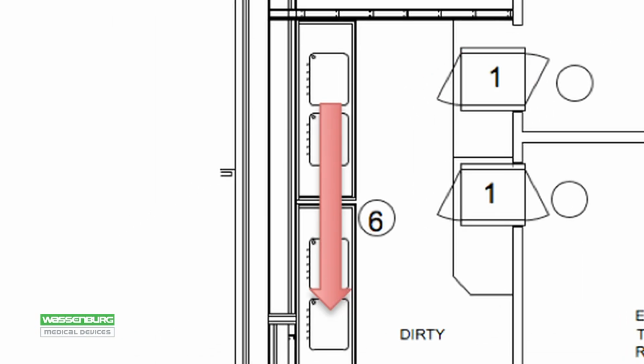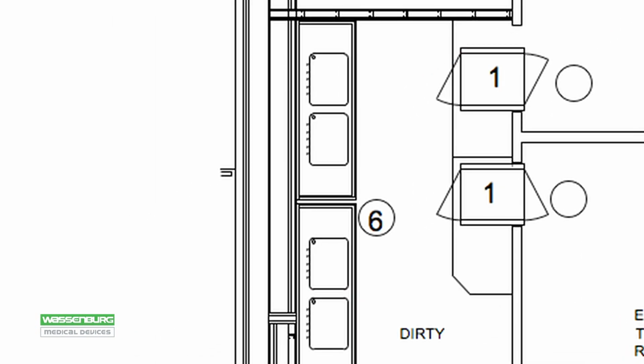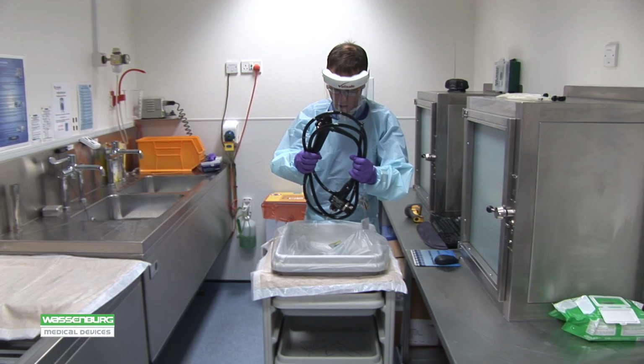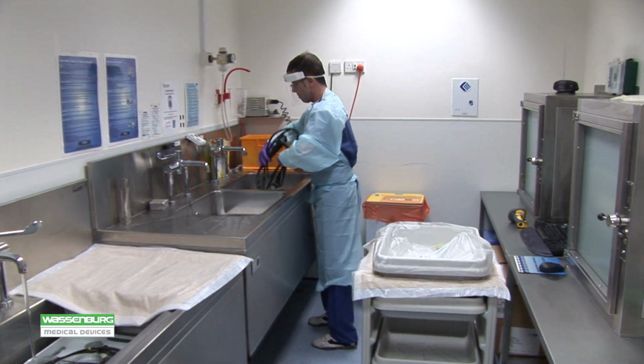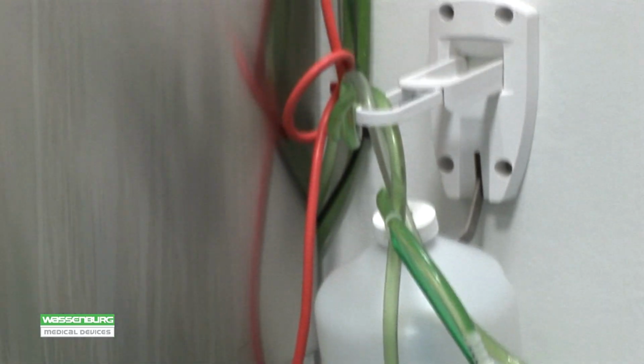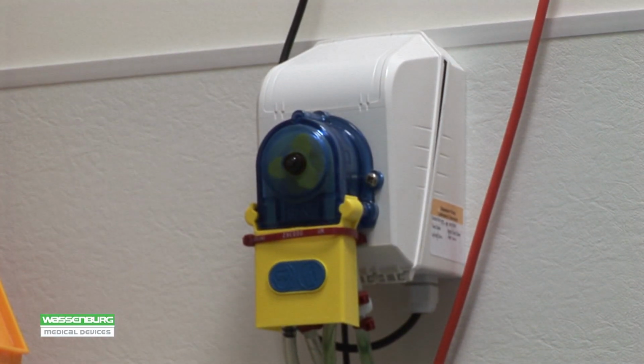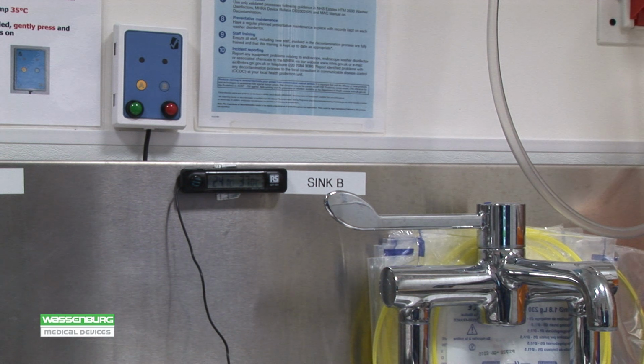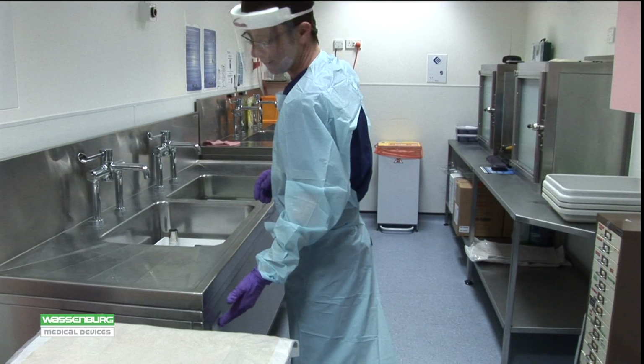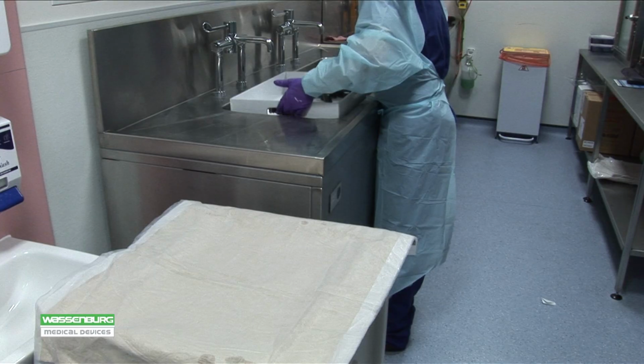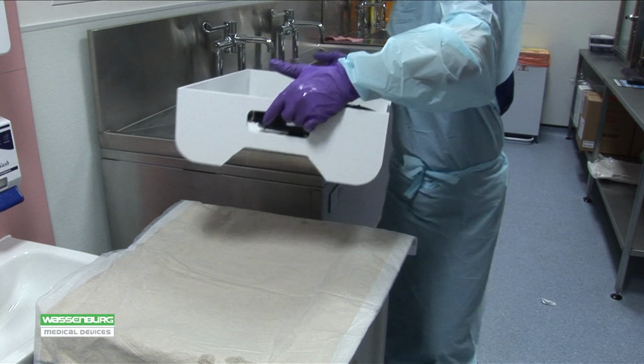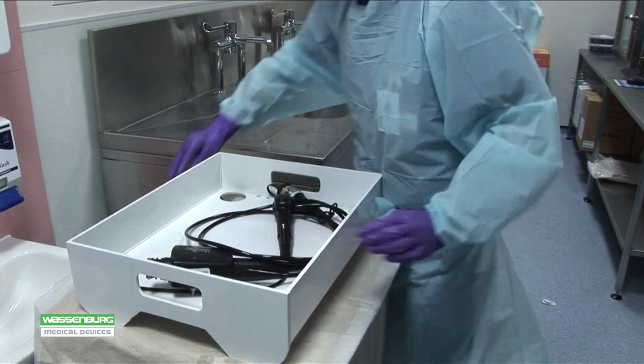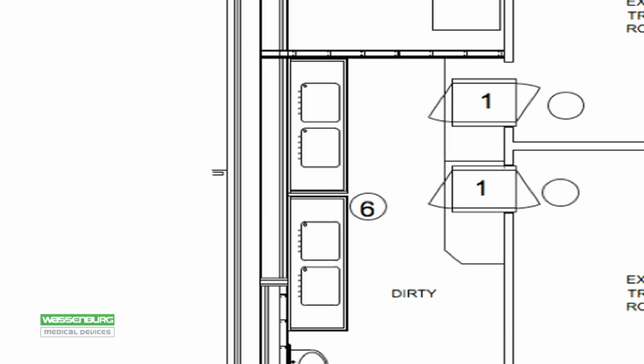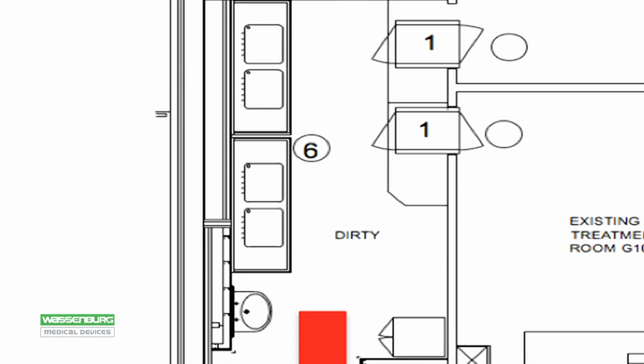Scopes are transferred to the adjustable height double sinks for manual cleaning, followed by rinsing in a separate bowl. Detergent is automatically dispensed in the correct volume to the wash sink by calibrated pump. Sink water temperature can be controlled using temperature indicators mounted above each sink. On completion of the manual cleaning process, scopes are transferred to the WD-440PT AERs in trays.